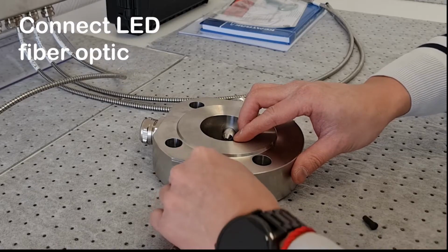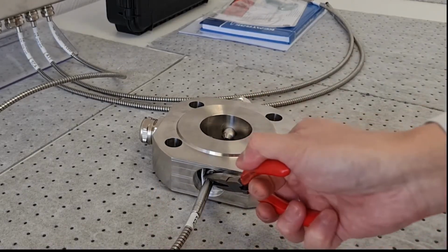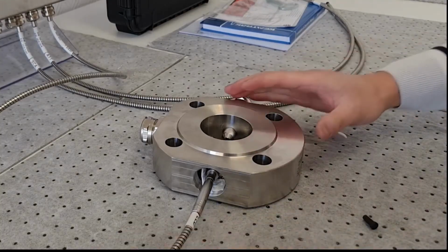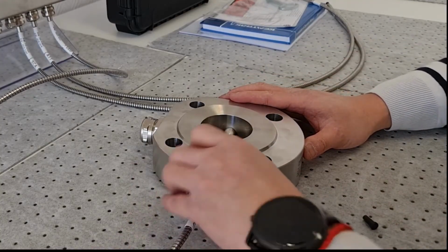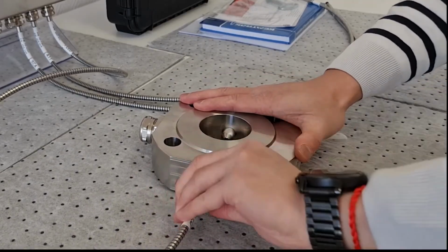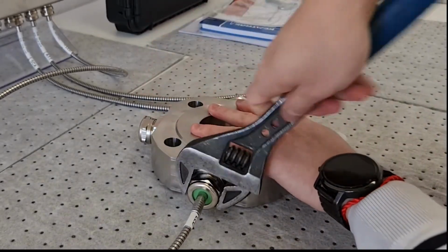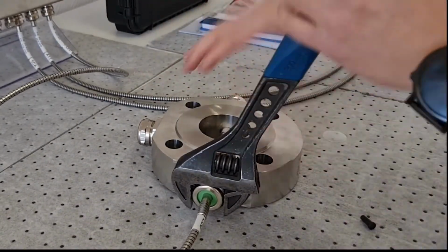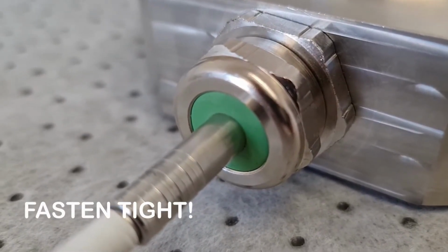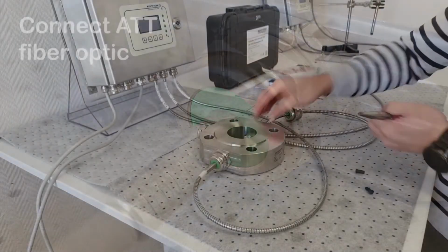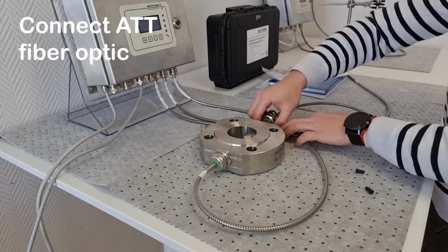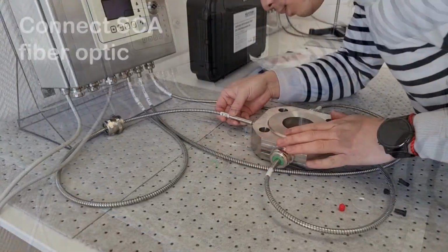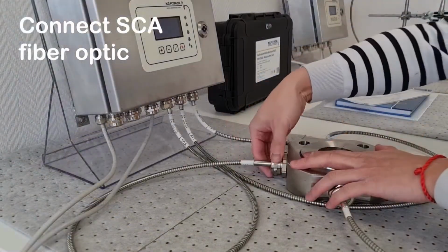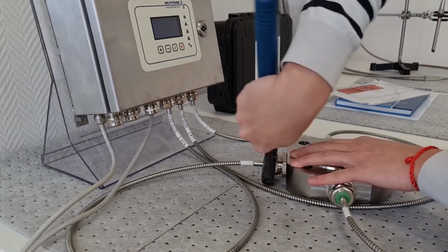Hand tighten the fiber optic connector to the measurement cell, then use a pair of long nose pliers to ensure the fitting is firmly attached. The cable glands on the measurement cell should be firmly and tightly fastened using a spanner. When tightened, there should be no gap visible between the cable gland sealing element and the fiber optic cable. The fiber marked ATT should be connected directly opposite to the cable marked LED. The fiber marked SCA should be connected to the measurement port located at 90 degrees to the other ports. The installation of the analyzer is almost complete.